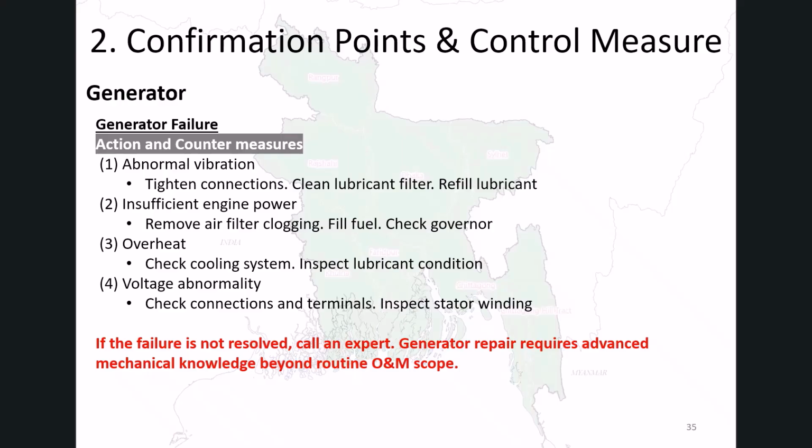First, abnormal vibration. If abnormal vibration is detected, operators should tighten all connections and inspect for loosened bolts or nuts. In addition, the lubricant filter should be cleaned and the lubricant should be refilled if necessary. These actions help reduce mechanical stress and prevent further equipment damage.